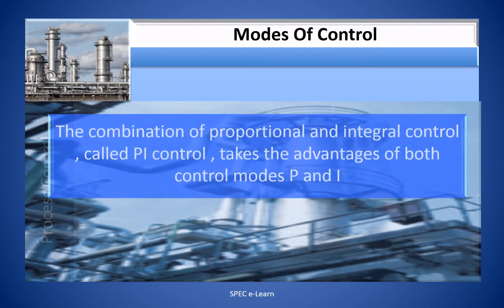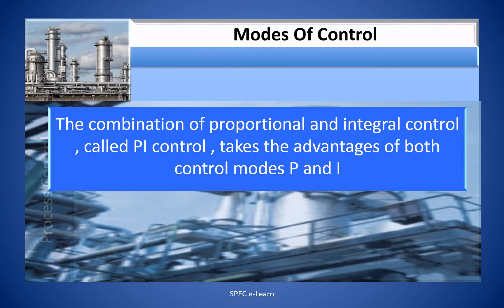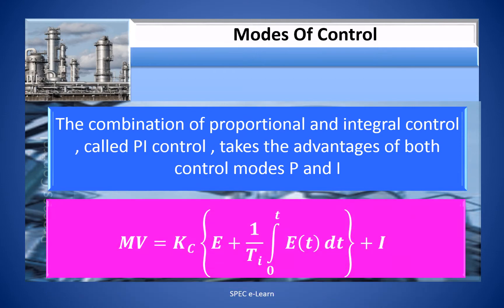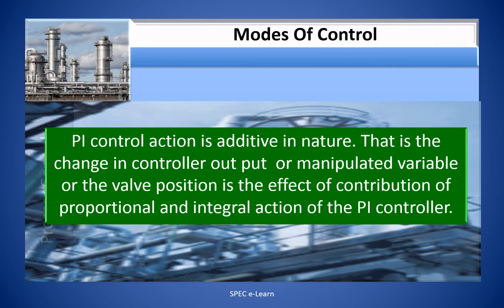The combination of Proportional Integral control, called PI control, takes advantage of both control modes — proportional and integral. The MV in the proportional integral mode is expressed as: MV = Kc × [e + (1/Ti) × integral from 0 to t of e dt] + i. The PI control action is additive in nature — that is, the change in control output or manipulated variable or valve position is the combined contribution of proportional and integral action of the PI controller.